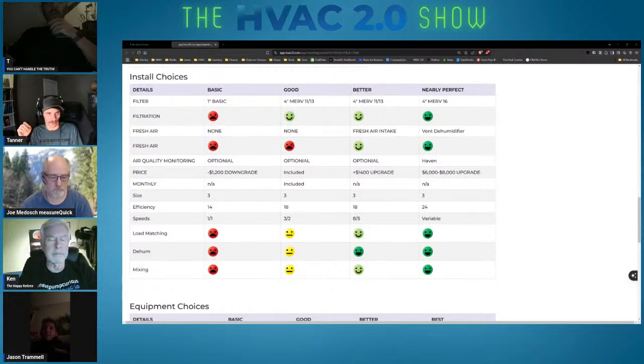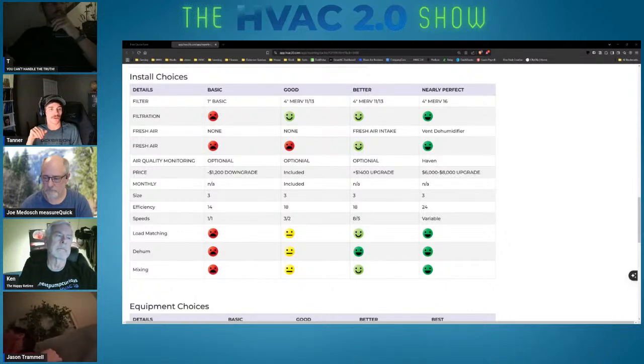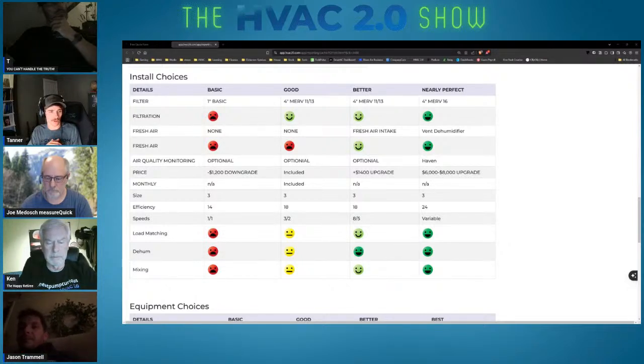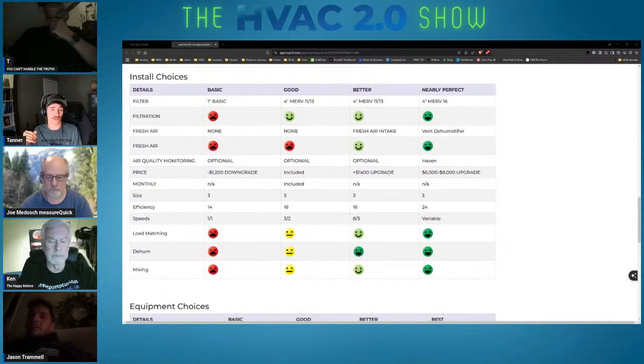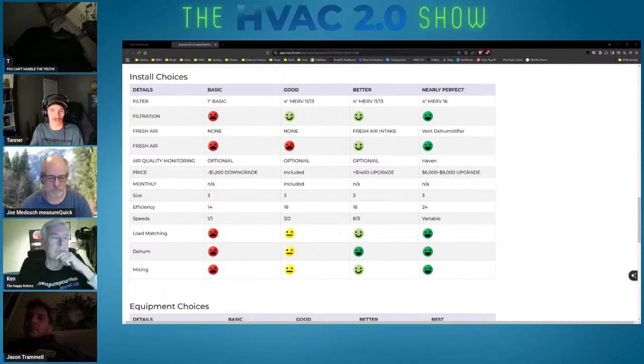There's kind of the argument that's been made, that if you're installing equipment, you need to do a duct design, figure out exactly what airflow at each register you should be getting, and then do a test and balance after the fact and so on. Sure, but I don't know what everyone else charges to do that, I charge quite a bit. So a lot of times it's easier to say, hey, what if we just get good equipment, take all that money we would have spent on testing and balancing and put it toward buying better equipment, and see if that's good enough for you. If it's not good enough, we can always make adjustments after the fact.